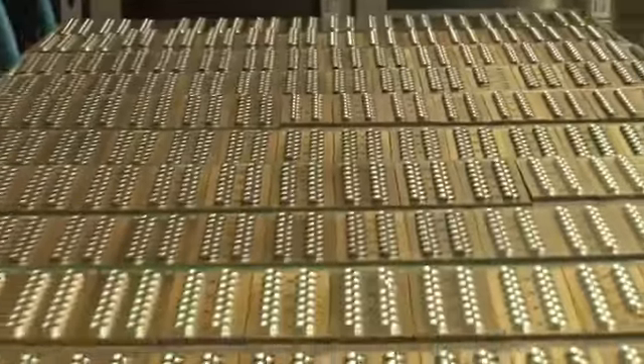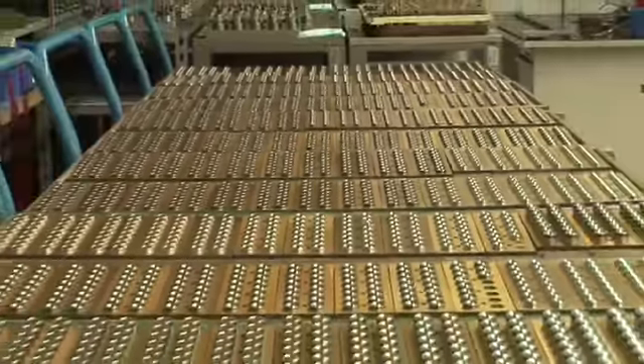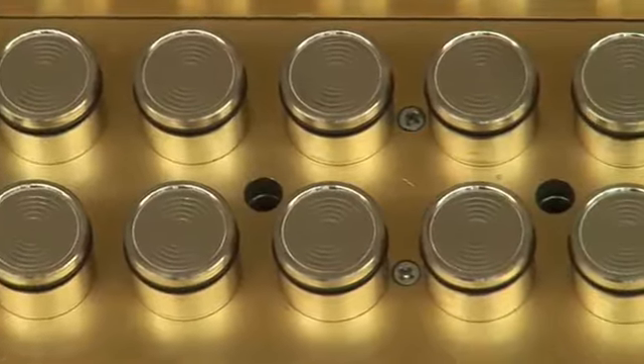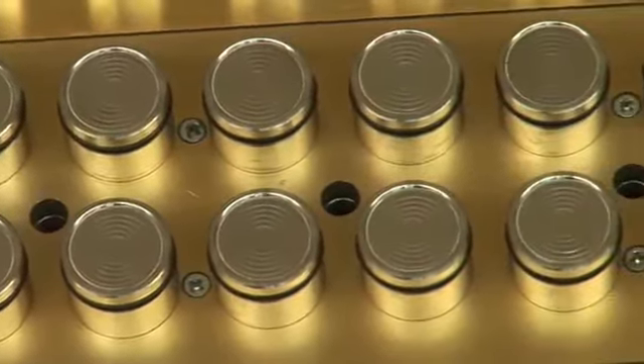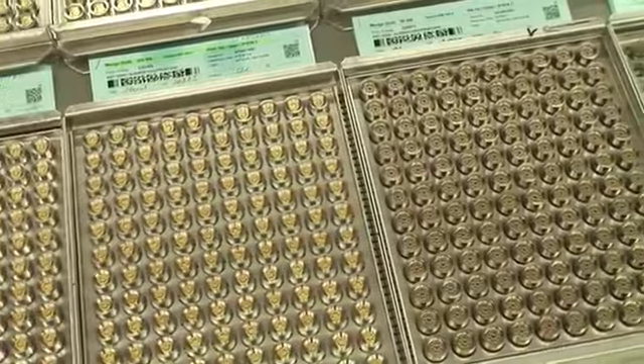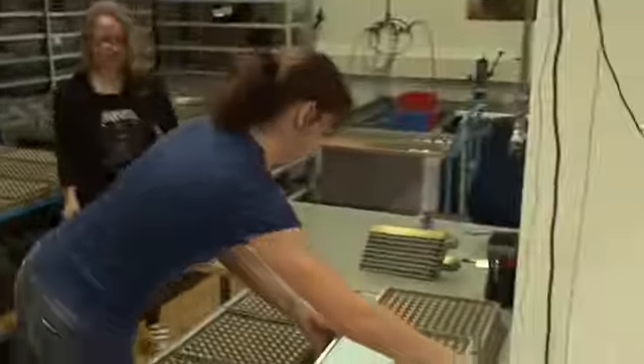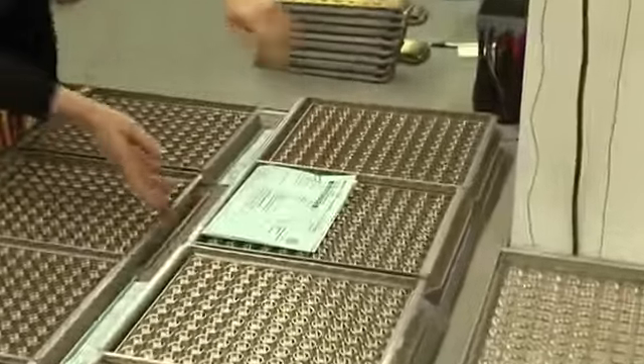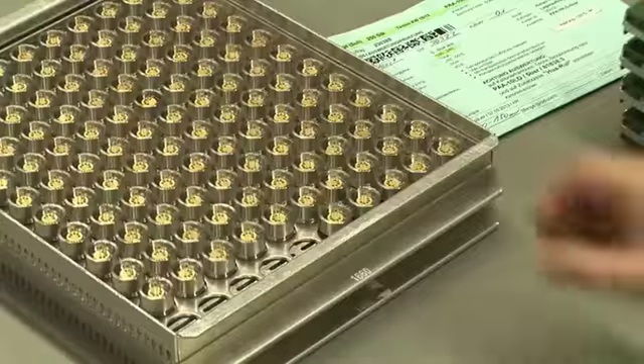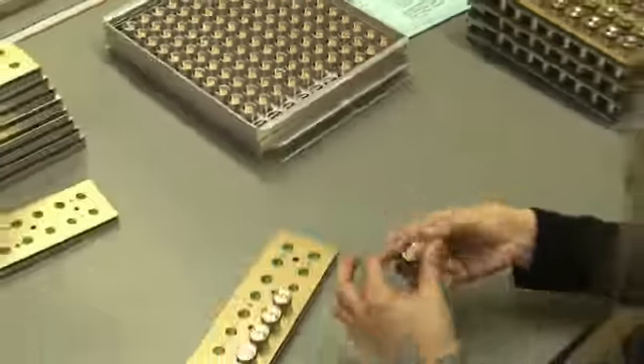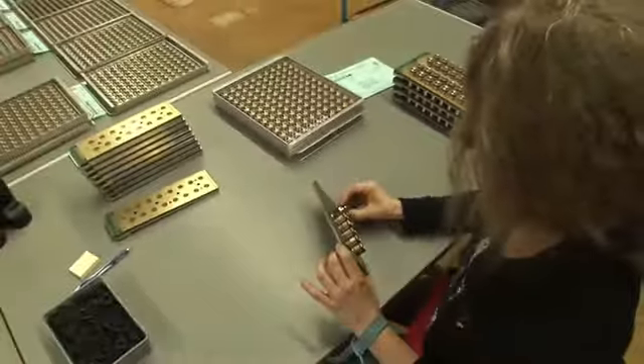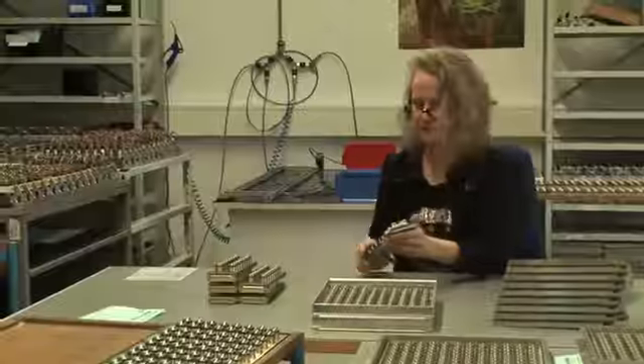Despite being industrially manufactured, sensor elements are just as unique in their behavior as humans. It's therefore necessary to examine each individual pressure transducer in testing stations and to determine its particular behavior. To do this, each unit is inserted into the measuring device by hand and exposed to different temperatures and pressures in climatic chambers until there are at least 300 measurement readings available for each sensor.